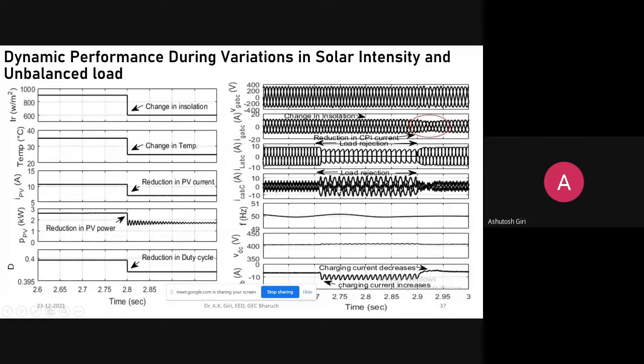This is the load rejection, and again load is injected, and we can see the changes on the compensator side. This is the device control, basically what we have used as a primary control. Device control, primary control is managing everything: voltage level control, frequency level control, power balance operation. Power balancing is done in the battery. All this VDC you can see here, VDC is fluctuating very small.